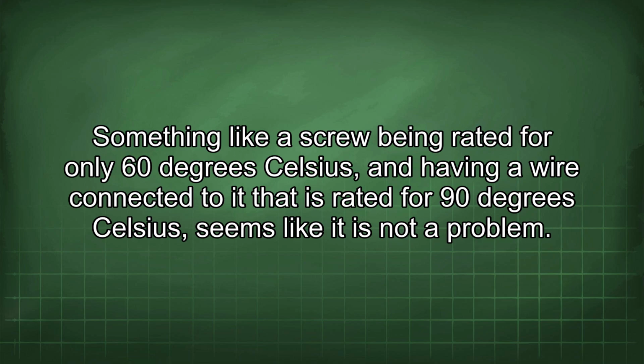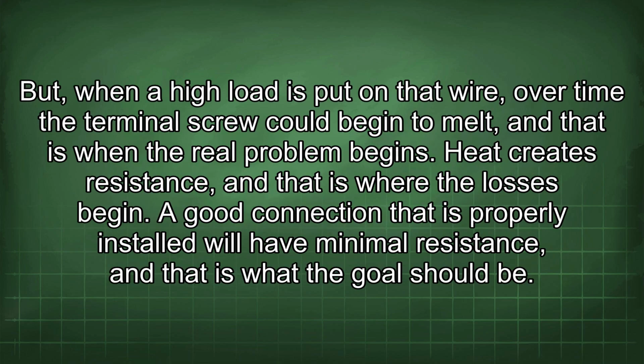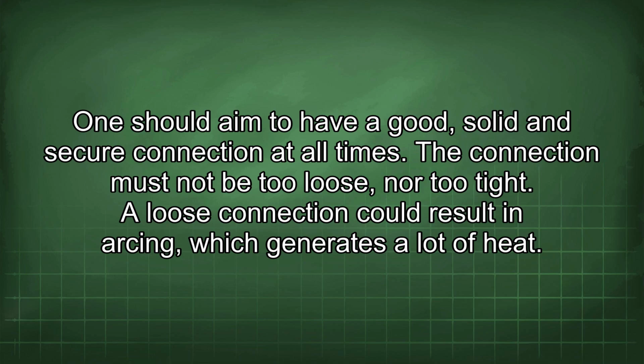Something like a screw being rated for only 60 degrees Celsius and having a wire connected to it that is rated for 90 degrees Celsius seems like it is not a problem. But when a high load is put on that wire, over time the terminal screw could begin to melt, and that is when the real problem begins. Heat creates resistance, and that is where the losses begin. A good connection that is properly installed will have minimal resistance, and that is what the goal should be. One should aim to have a good, solid, and secure connection at all times.